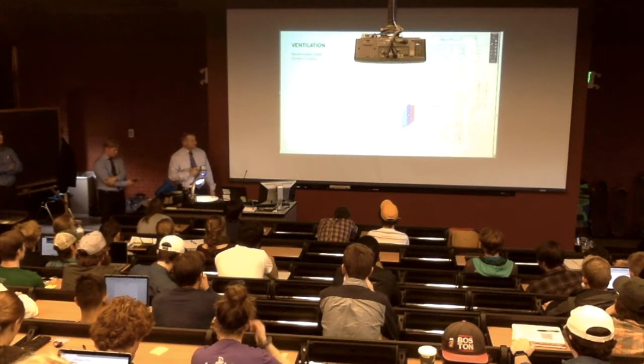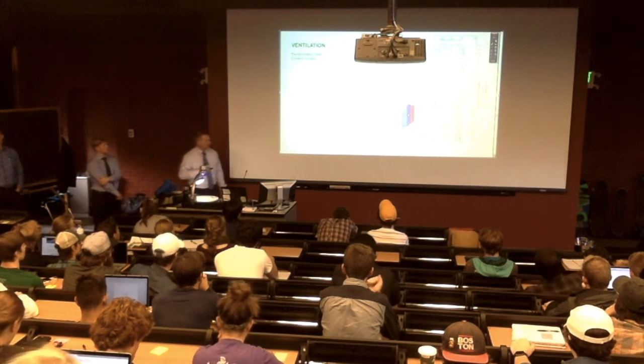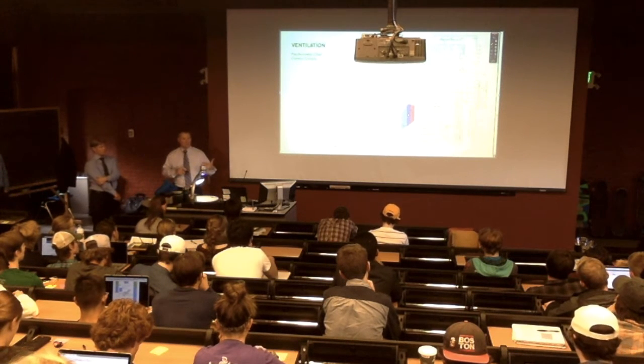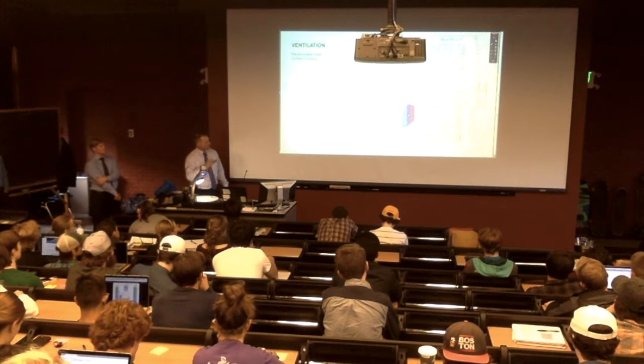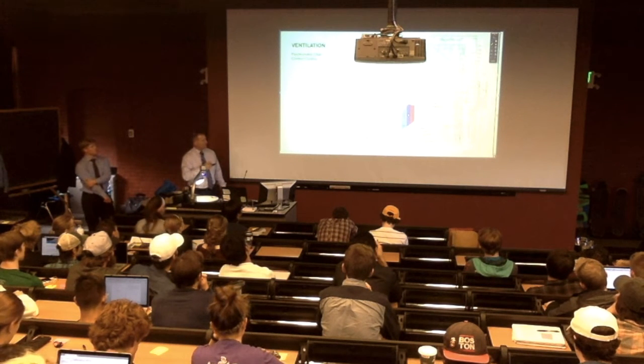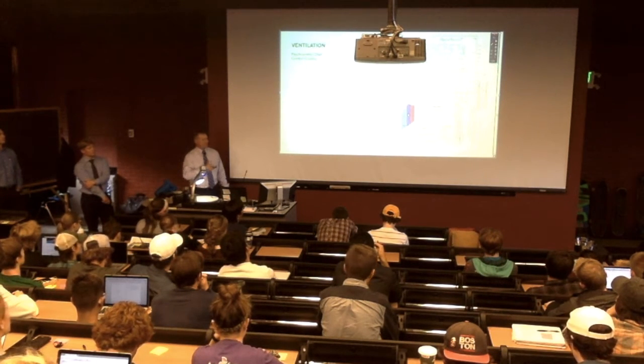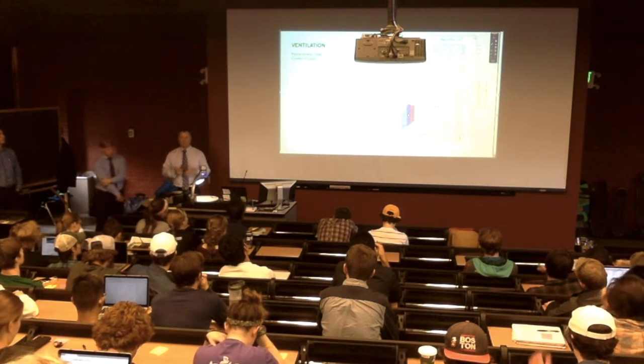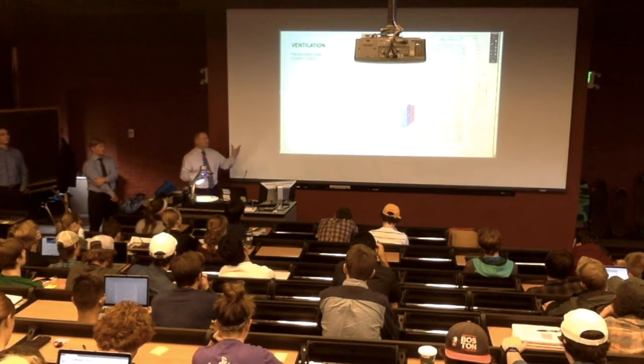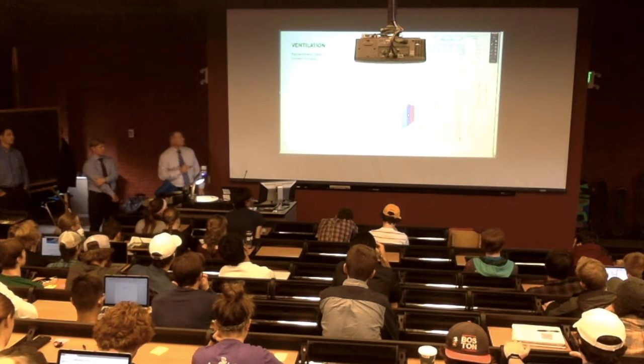Ventilation, hopefully you'll get the chance to take a course in this, but this is a psychrometric chart. The x-axis is the dry bulb temperature, which is the temperature that you read on your thermometer. This axis, it's not exactly the y-axis, but this axis is the dew point temperature, and this is actually the dew point of air. So as you cool air down and it hits the dew point line, that's when it condenses out. It's what you see on the glass in the summertime. So you have a cold glass with ice in it, and the air hits it. It's all based upon the psychrometric chart. This is the properties of air and water. So we use that to understand what the cooling requirements are for the building.